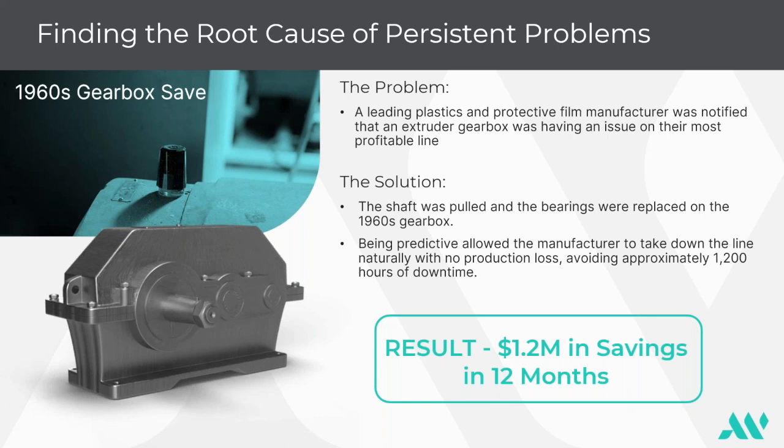It was some old Hyatt bearings that they had installed on this input shaft, and it was a few thousandths over what the clearance was. The point of contact that I work with at this facility is very knowledgeable, so he was able to go and look up on his own what those radial clearances were actually supposed to be for that bearing, and leverage that data versus what the as found was when they did the actual lift test.